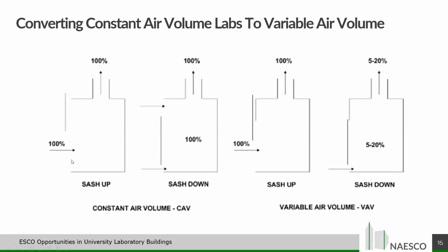And this diagram is depicting a fume hood, and on the left is a constant air volume fume hood. And when the fume hood is being used and the sash is up, you've got 100% exhaust coming through that sash opening, going up the exhaust duct into the plenum and out the exhaust stack into the atmosphere. And you're maintaining your face velocity across that opening so the users are safe. On a constant air volume fume hood, when you close the sash, there's a bypass above the sash that opens up. So even though the sash is closed, you're still exhausting 100% of the air through that fume hood, up the exhaust duct and out the exhaust stack. So there's no change in exhaust volume on a constant air volume fume hood, as one would suspect.